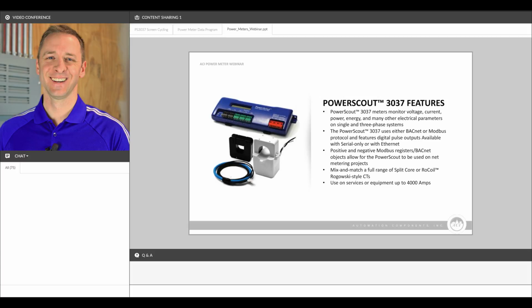This device is going to communicate to your BMS or control system using BACnet or Modbus protocol. And it also features a digital or a pulse output over a serial connection or an Ethernet connection. It can be used for net metering. So if you've got some on-site electrical generation, you can use this device for net metering applications. And it can be used with any or all of the CTs that are accompanying. You can mix and match CTs, and so you can pair the proper CT with the device depending on the specifics of your application. And it can be used on services or equipment up to 4,000 amps.